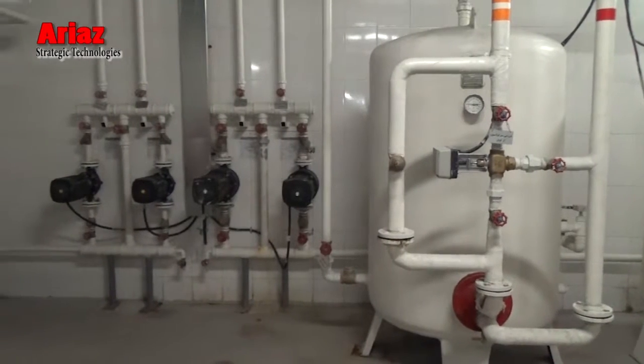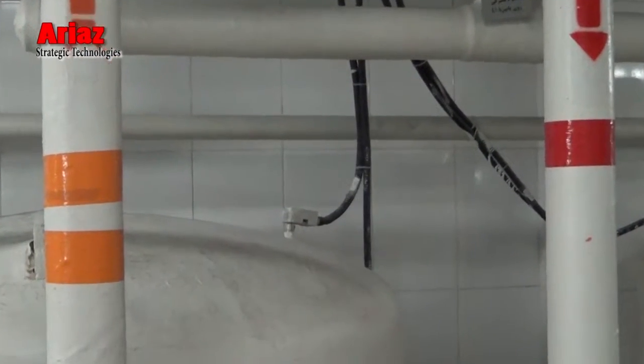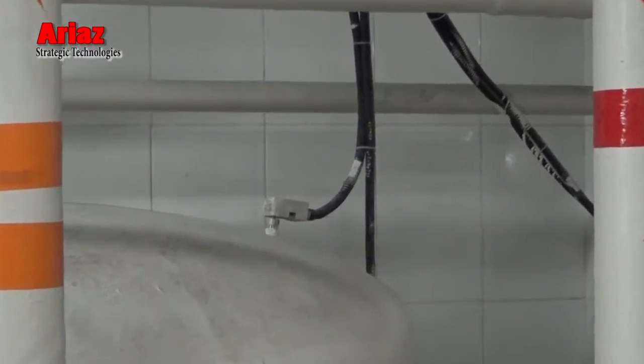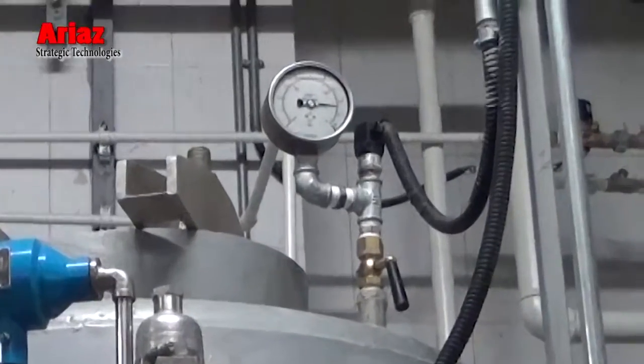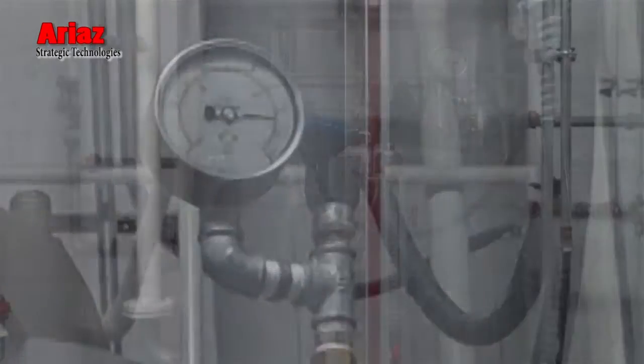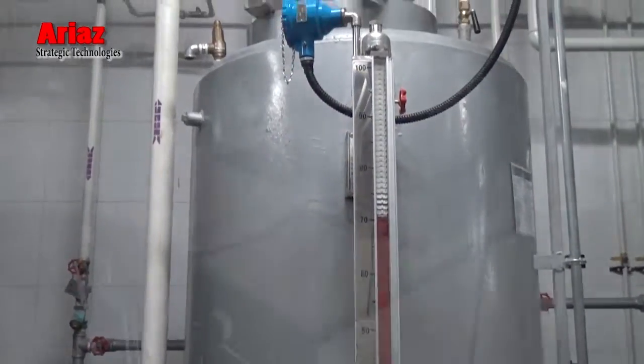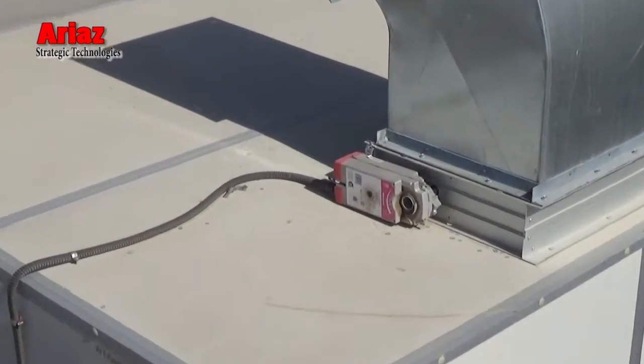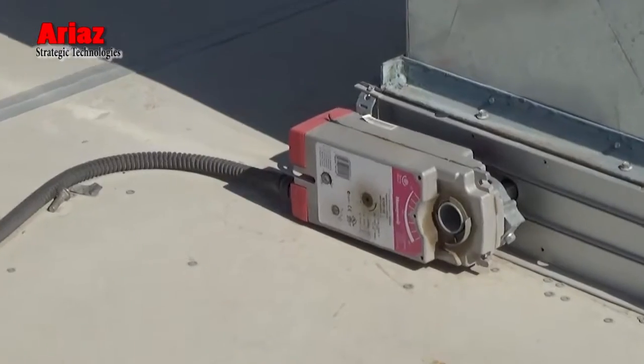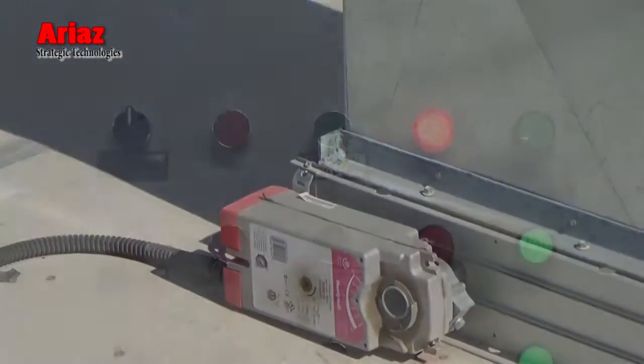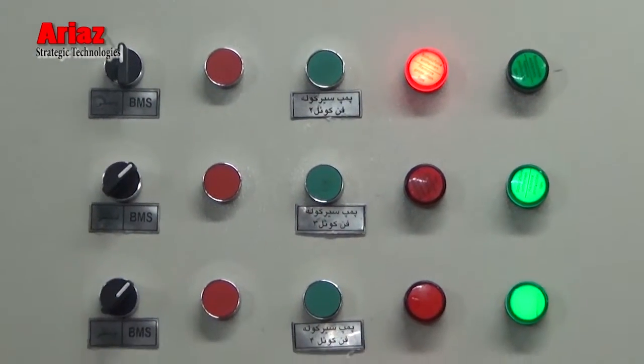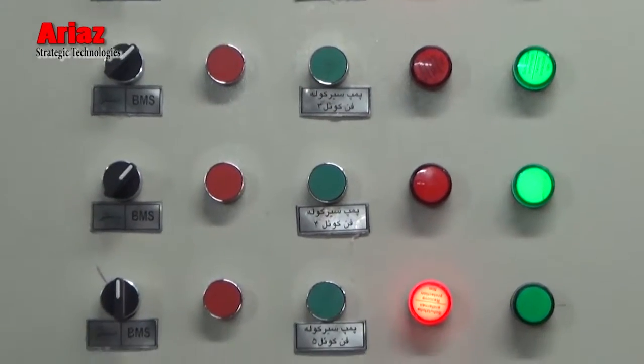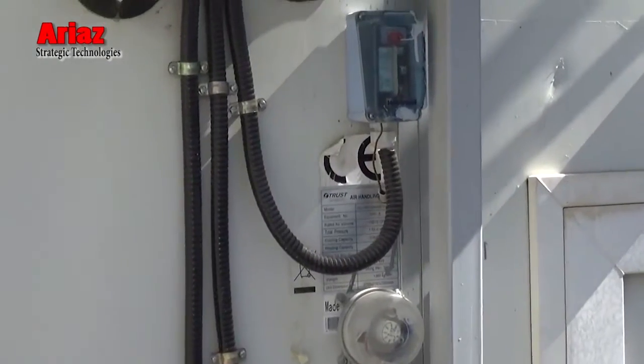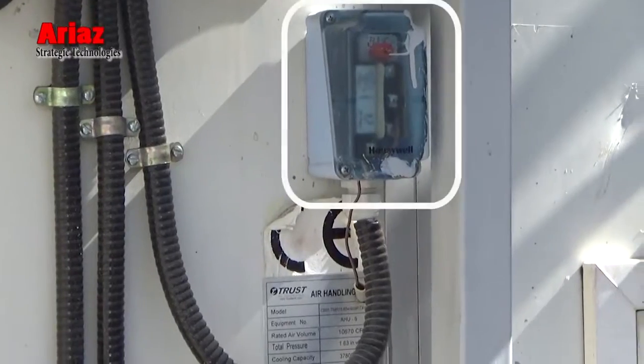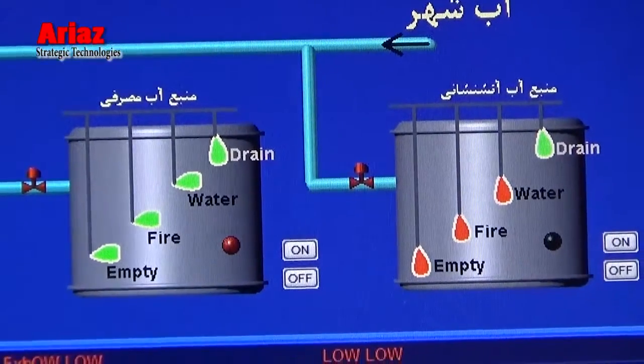We have used a lot of analog sensors in this project, such as thermal sensors to measure temperature, pressure sensors to detect the inside pressure, the detection of water levels, and the opening and closing of the exhaust air dampers in the air handling units. Digital sensors for detection of open and closed keys, switches, pressure switches, sensors for freeze protection, and to determine the water level in the reservoir's tank.